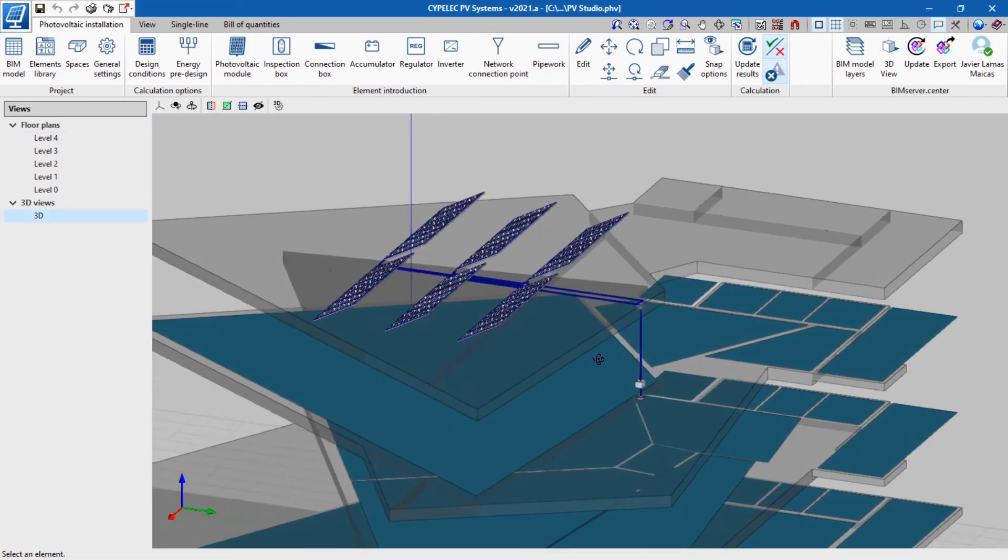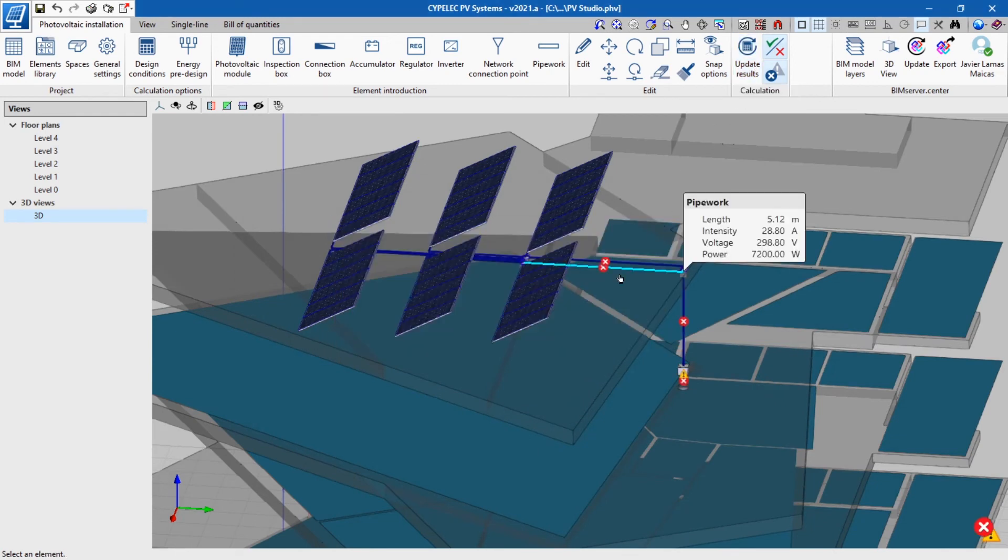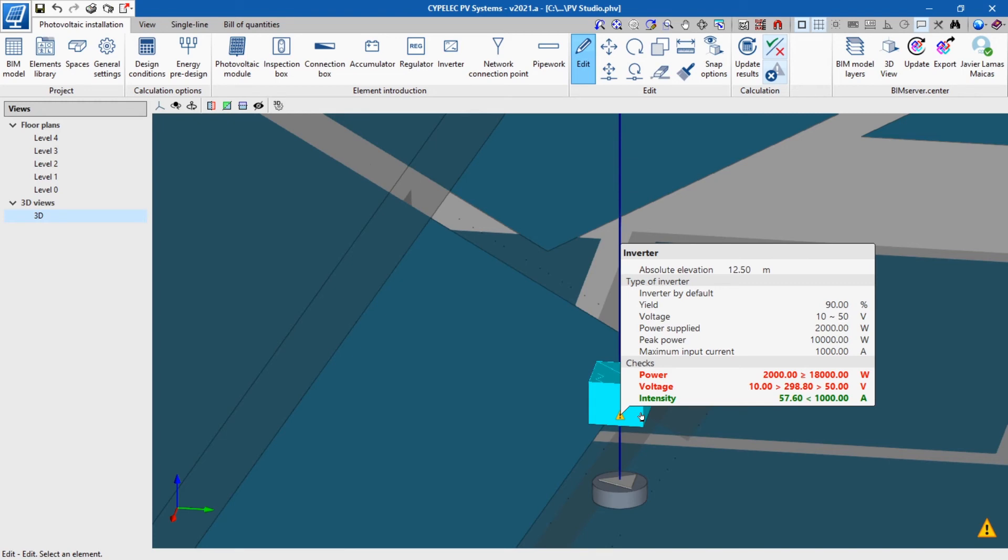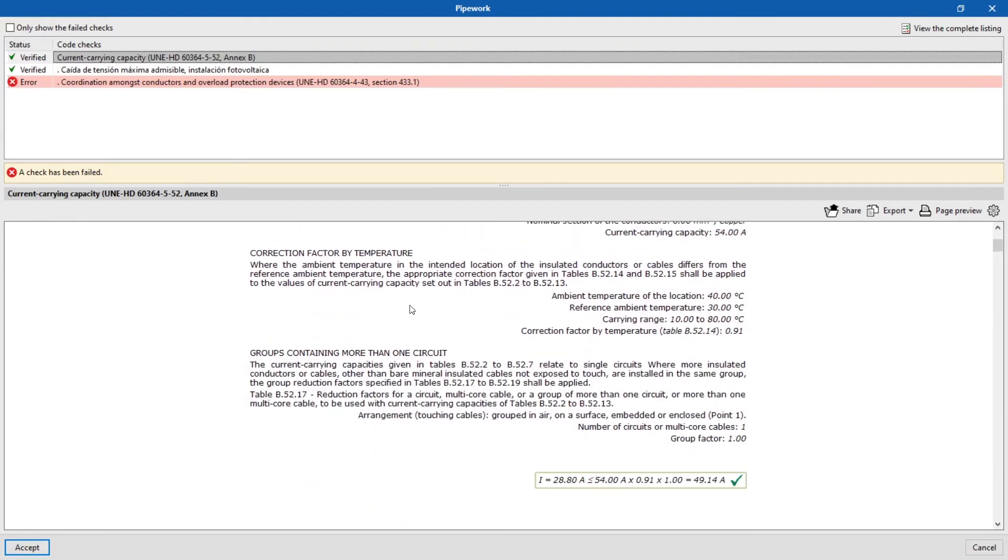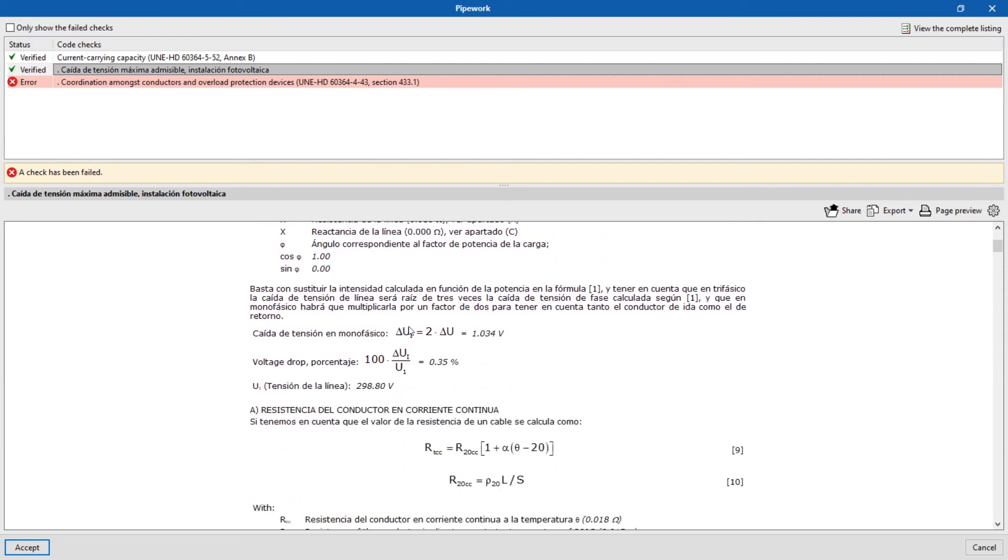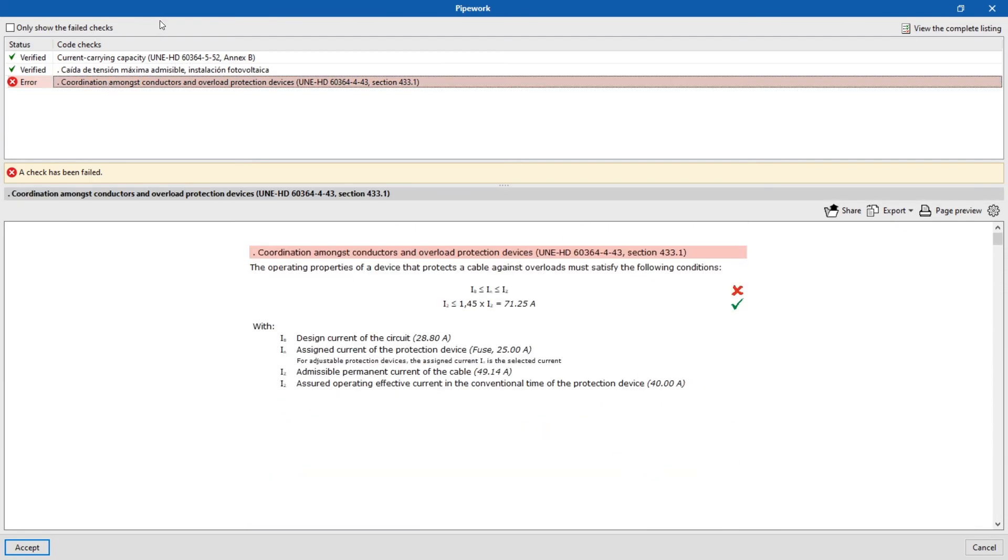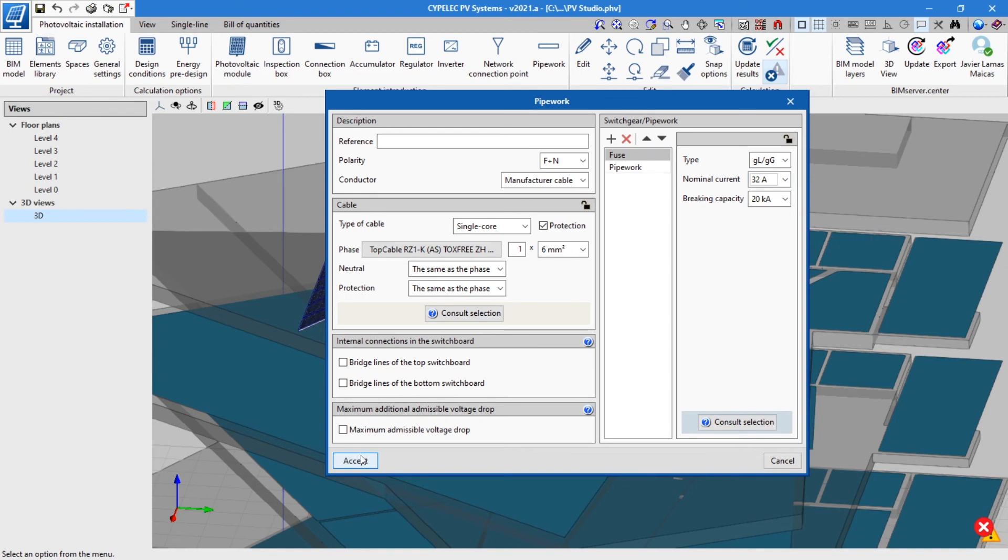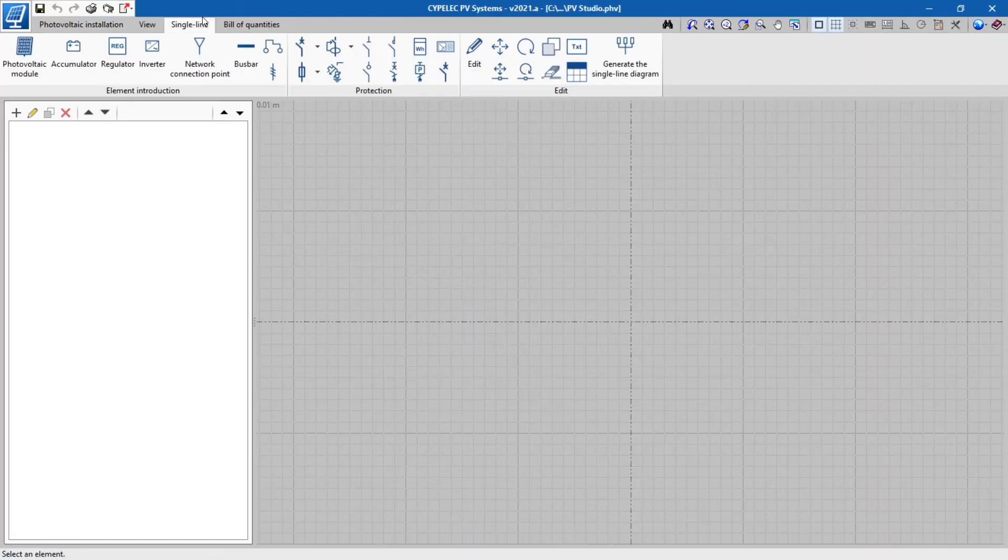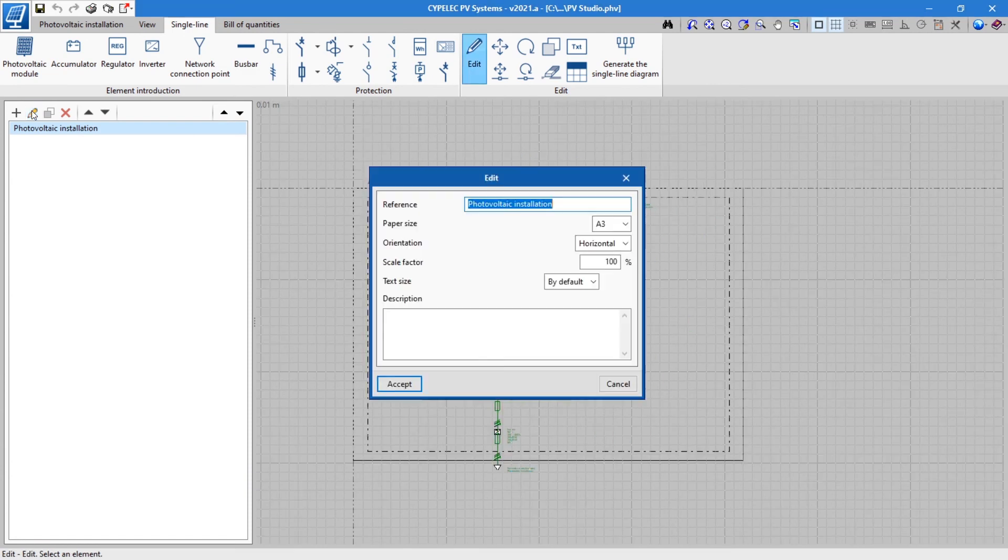Once all the elements have been connected up to the network connection point, the installation will be calculated and the program will display error warnings on conductors that do not meet the requirements. Clicking on each conductor will show the checks that have been performed on it. With this information, conductors that do not comply or those that exceed the compliances can be modified according to the designer's criteria. Furthermore, the program allows a single line diagram of the installation to be automatically created and placed on the most suitable type of plan.